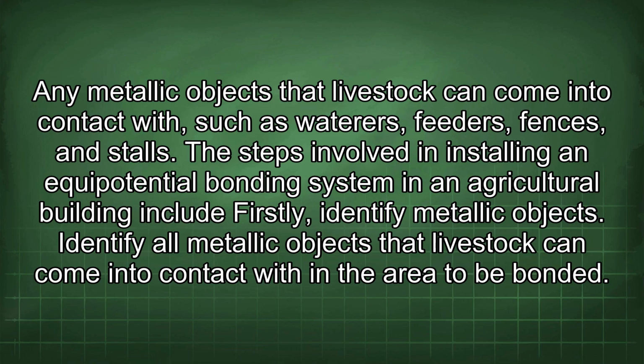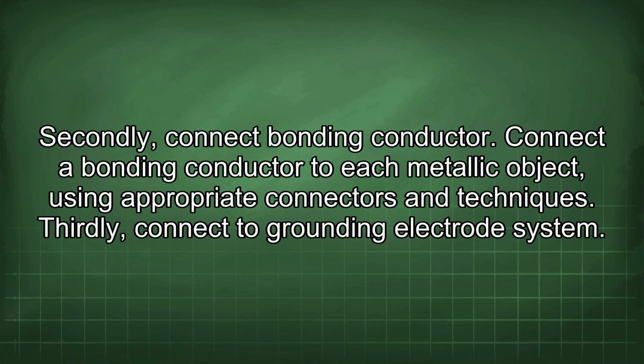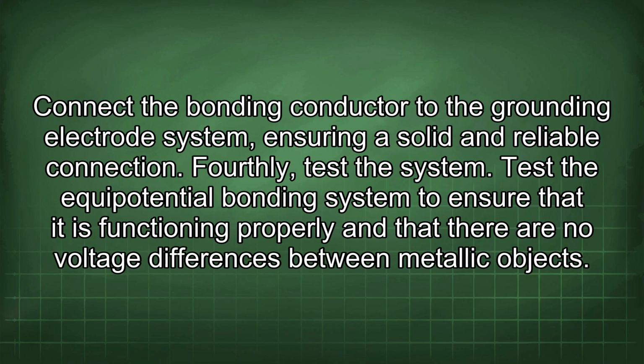The steps involved in installing an equipotential bonding system in an agricultural building include, firstly, identify metallic objects. Identify all metallic objects that livestock can come into contact with in the area to be bonded. Secondly, connect bonding conductor. Connect a bonding conductor to each metallic object using appropriate connectors and techniques. Thirdly, connect the grounding electrode system. Connect the bonding conductor to the grounding electrode system, ensuring a solid and reliable connection. Fourthly, test the system. Test the equipotential bonding system to ensure that it is functioning properly and that there are no voltage differences between metallic objects.